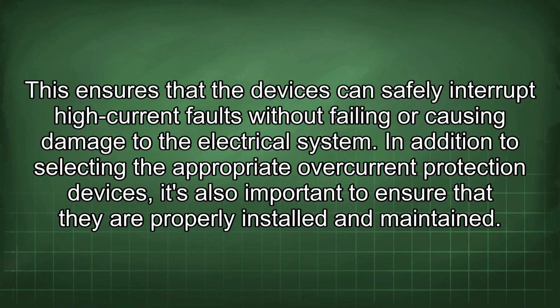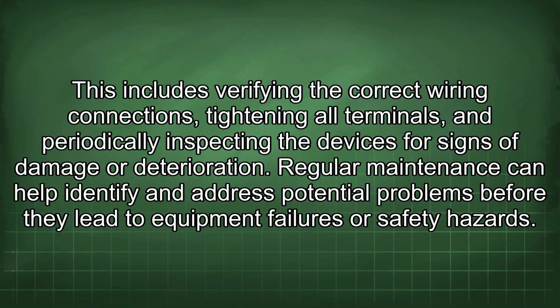electrical system. In addition to selecting the appropriate overcurrent protection devices, it's also important to ensure that they are properly installed and maintained. This includes verifying the correct wiring connections, tightening all terminals, and periodically inspecting the devices for signs of damage or deterioration. Regular maintenance can help identify and address potential problems before they lead to equipment failures or safety hazards.